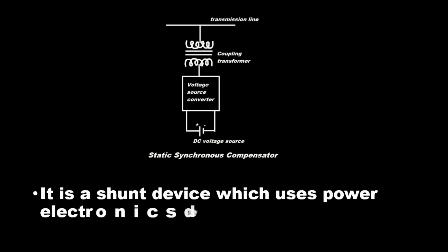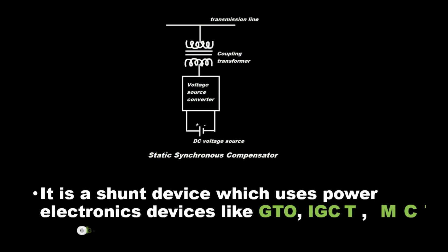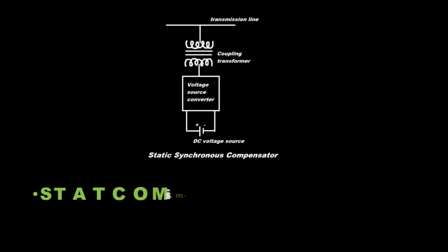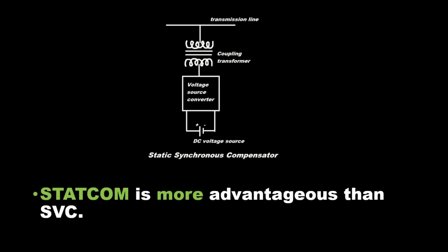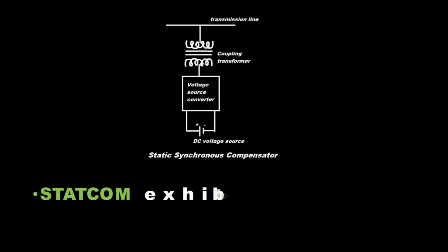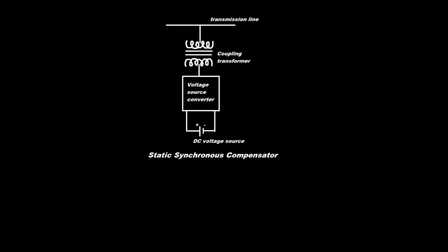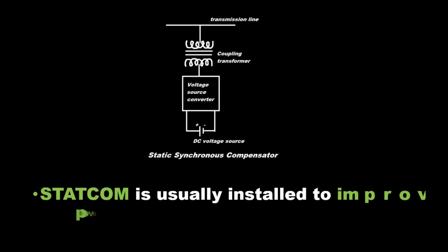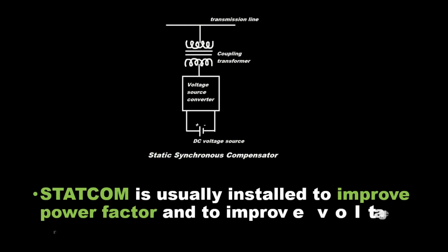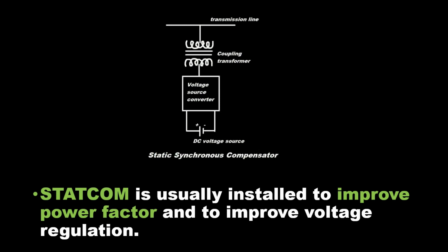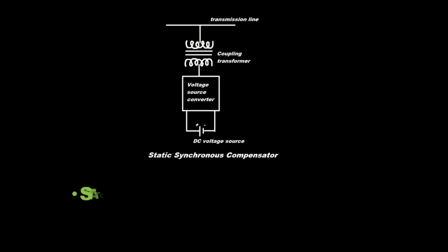It is a shunt device which uses power electronics devices like GTO, IGCT, MCT, or IGBT. STATCOM is more advantageous than SVC. STATCOM exhibits constant current characteristics and is usually installed to improve power factor and voltage regulation.